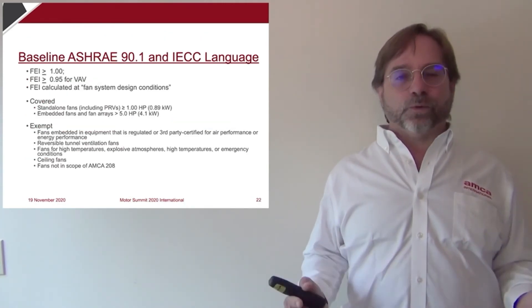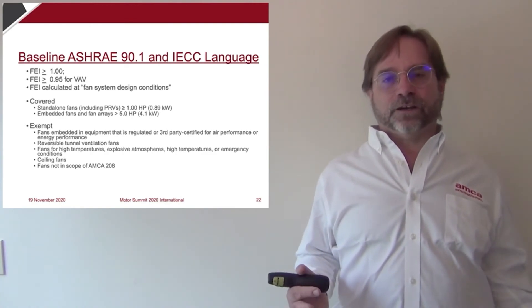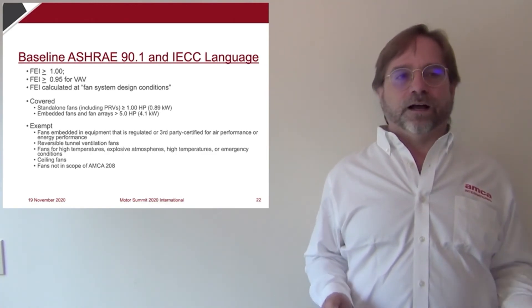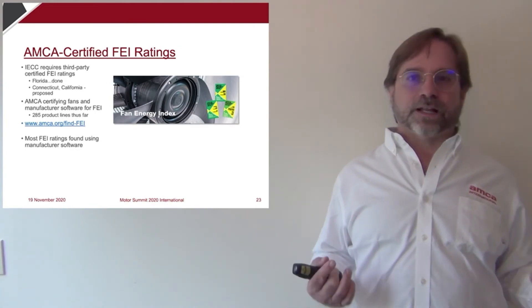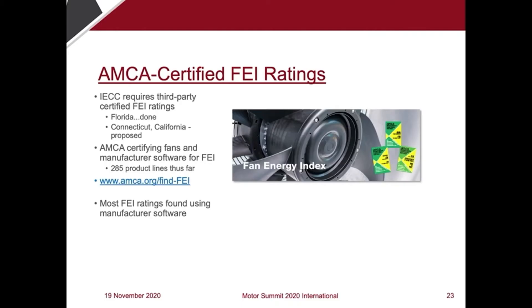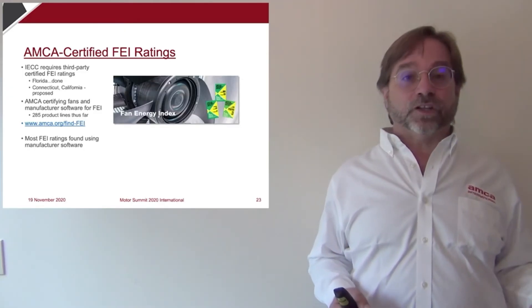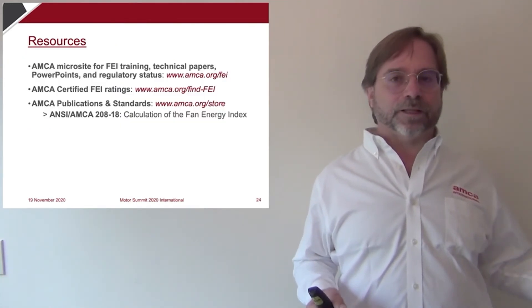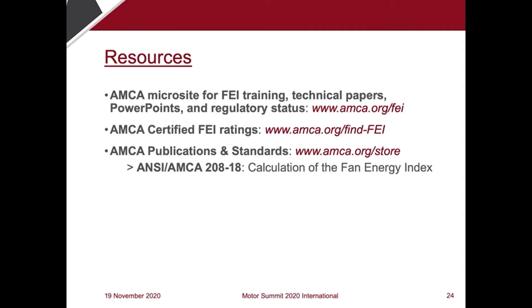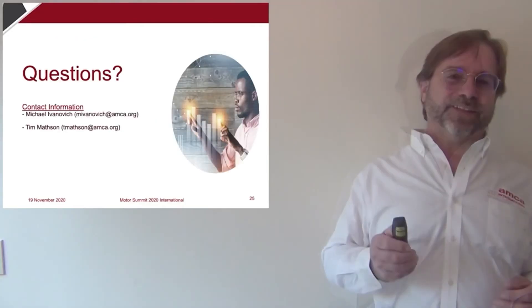In terms of the exact language that's used in the model energy codes and standards, I'm going to skip over that. But it is worth mentioning that the International Energy Conservation Code, IECC, is different from ASHRAE in that it requires independently verified or third-party certified FEI ratings. And towards that, AMCA does certify FEI ratings predominantly by certifying manufacturer software. And the URL shown here provides an easy way to find where fans are currently certified. Thank you very much.